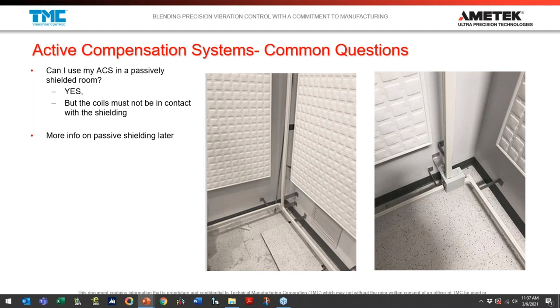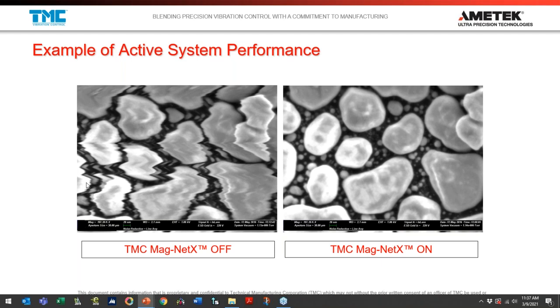However, the coils cannot be in contact with the shielding. Here's a typical approach: the six-sided coil box is mounted in the shielded room and stood off from the passive shield using standoffs, so the cables from the active cancellation system are not in contact with and are sufficiently standing off from the passive shield. This is an example of the performance you'll see from a scanning electron microscope using an active cancellation system — you can see the typical horizontal AC waves in the image, then once you turn on the cancellation system, the disturbance field is immediately suppressed and you get a much clearer image.